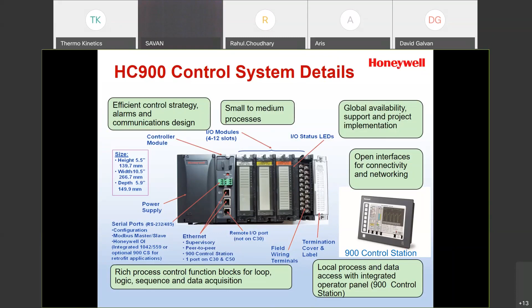Okay, it does have its own software. See the Control 900 station that you can connect to it. It's peer-to-peer connected to that, but it also has universal inputs and universal outputs. Now the difference between this and the PLC: this is safety rated. This is a SIL 2 system. Okay, so if you need a safety manager, this is good up to SIL 2. All right. Again, it's only function block because it's a PAC. You don't get ladder, none of that stuff. It's solely function block, but it is SIL 2. All right, HC900.